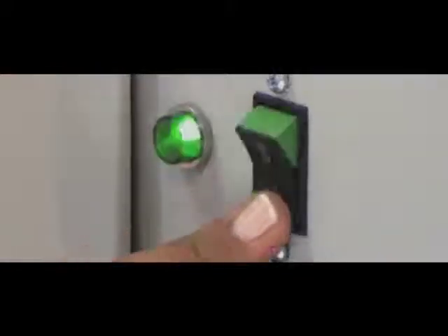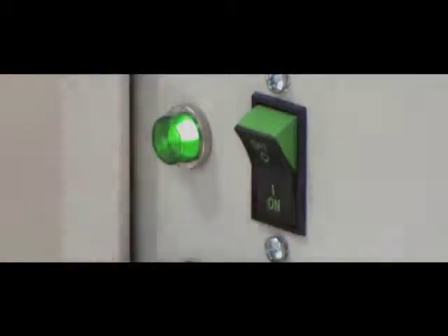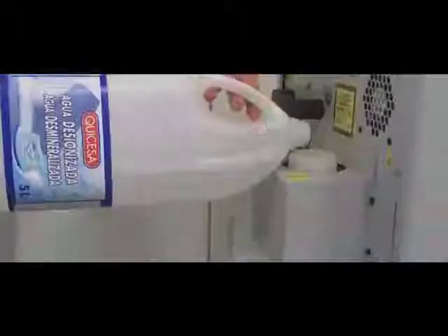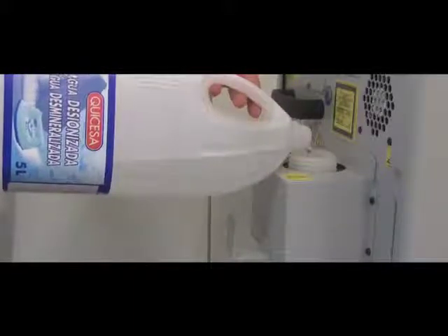In the back of the device, you will find the on-off button, the interlock key, the foot pedal insert, the device filter, and water canister. The water canister should only be filled with distilled or deionized water and should be checked weekly. The back filter is easily removed and cleaned with a vacuum or canned air once per week.